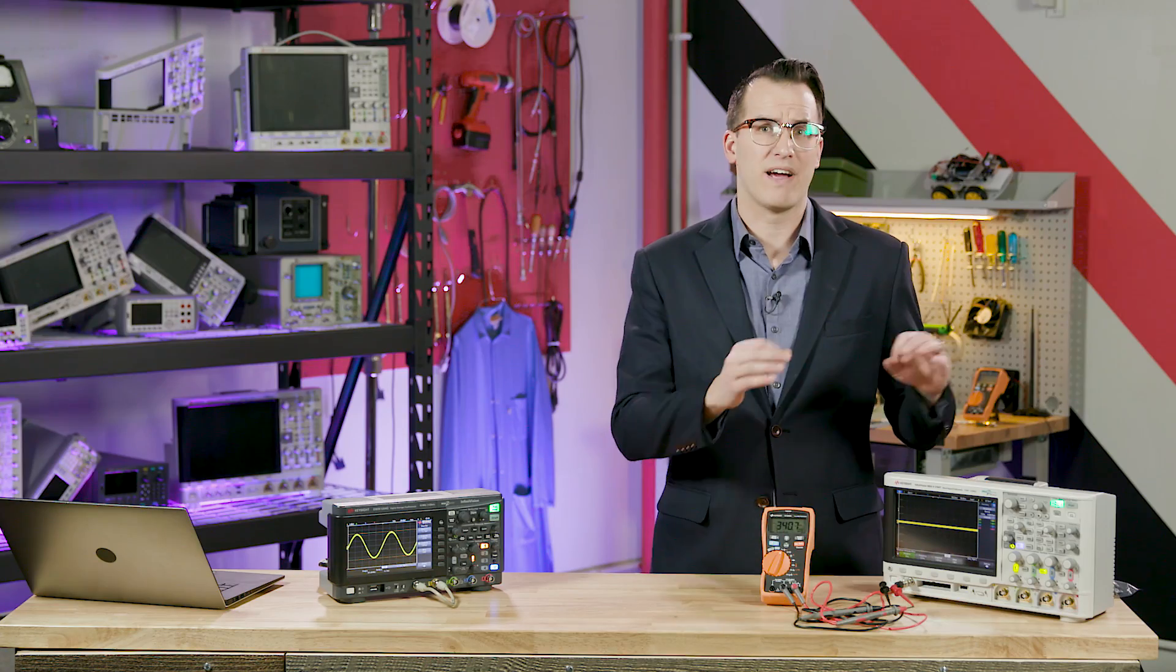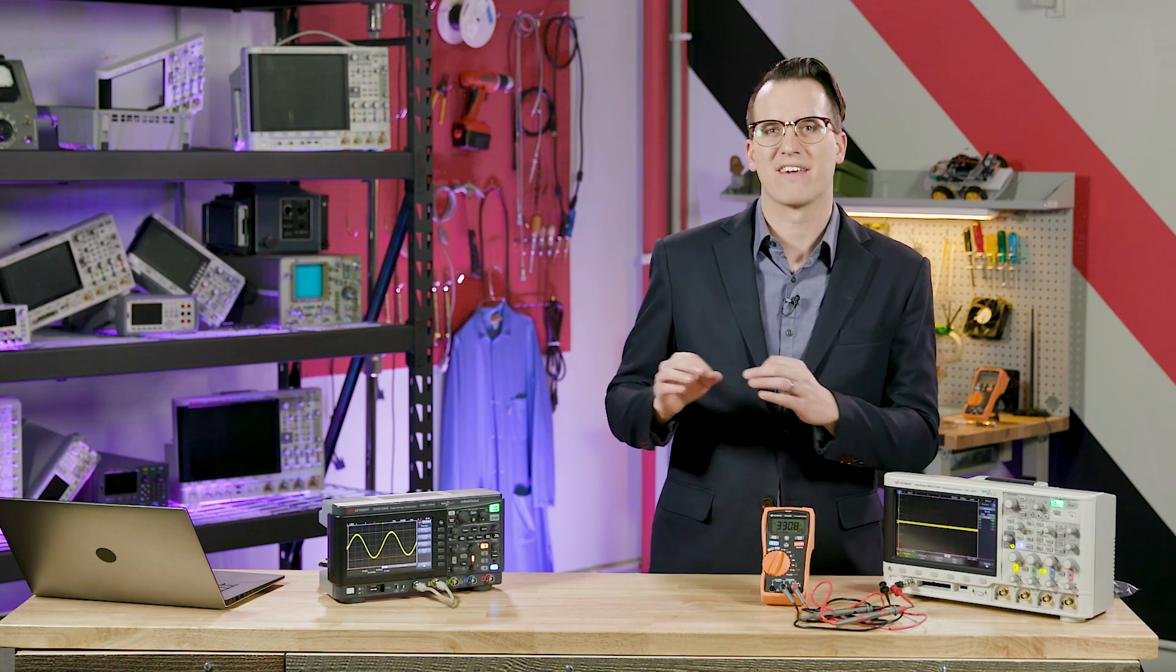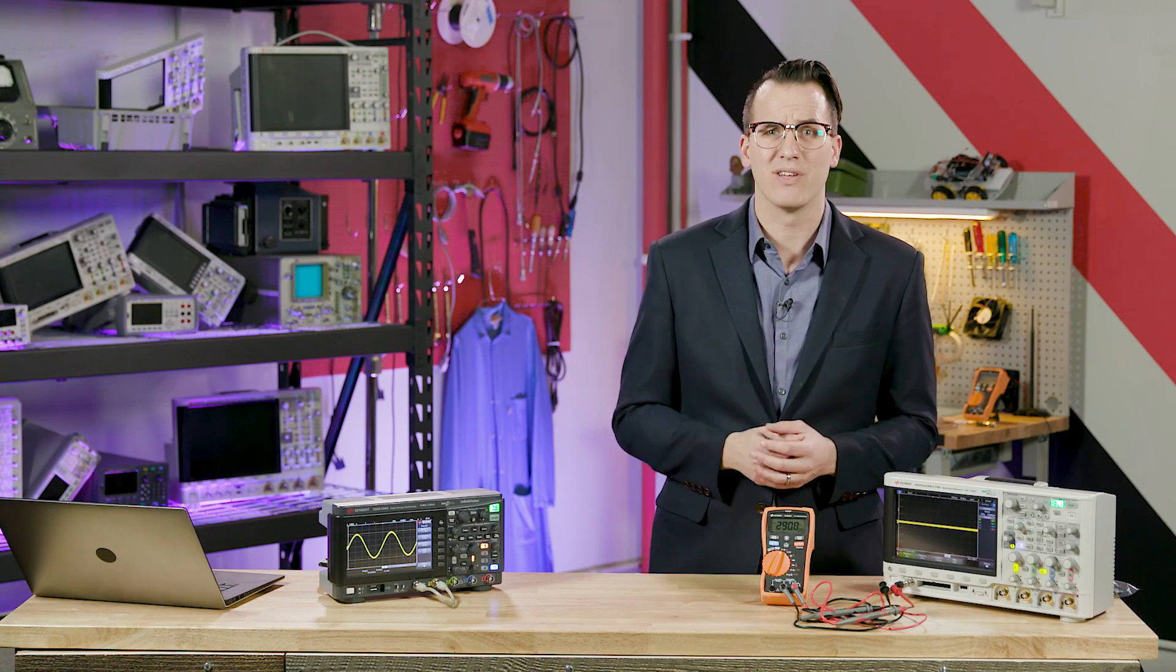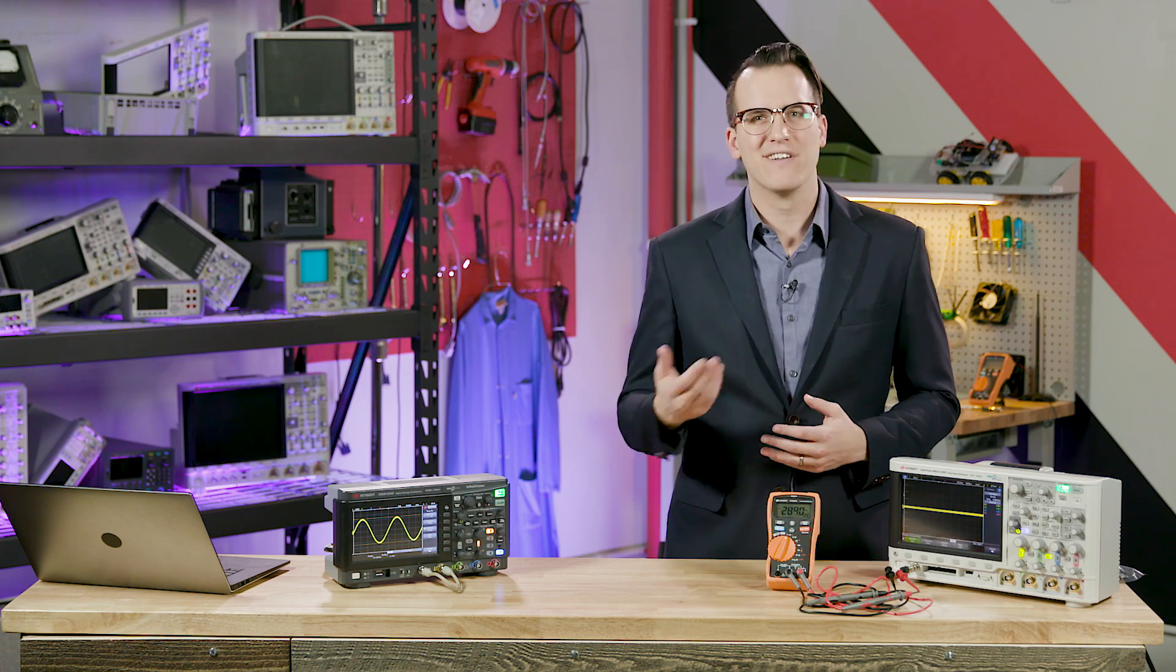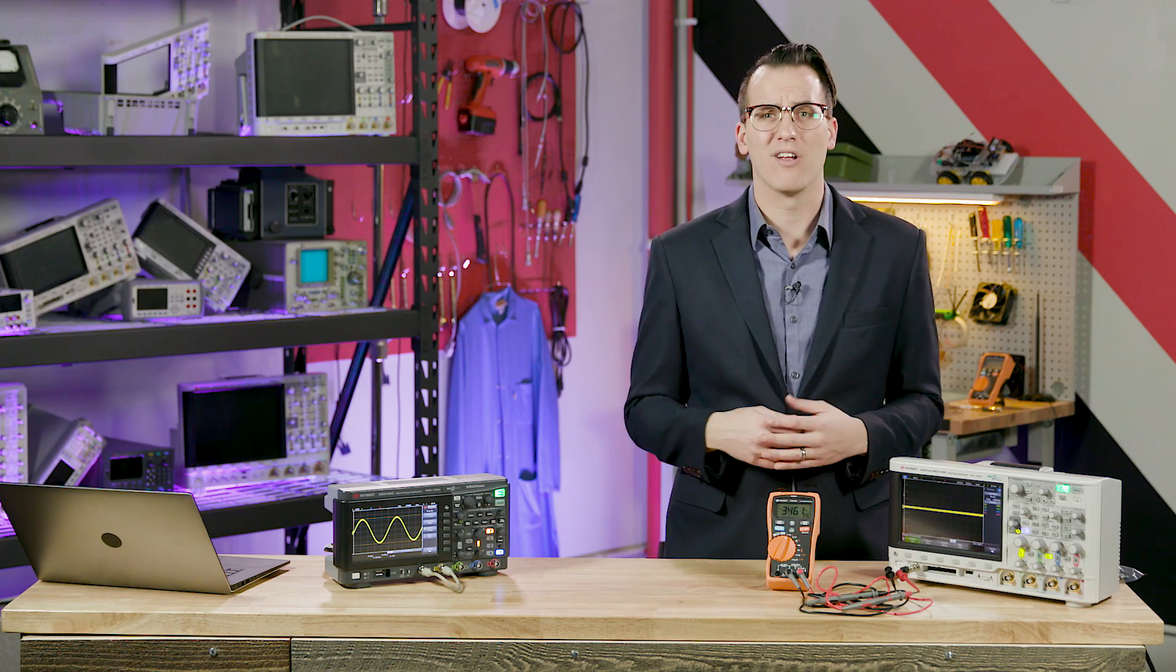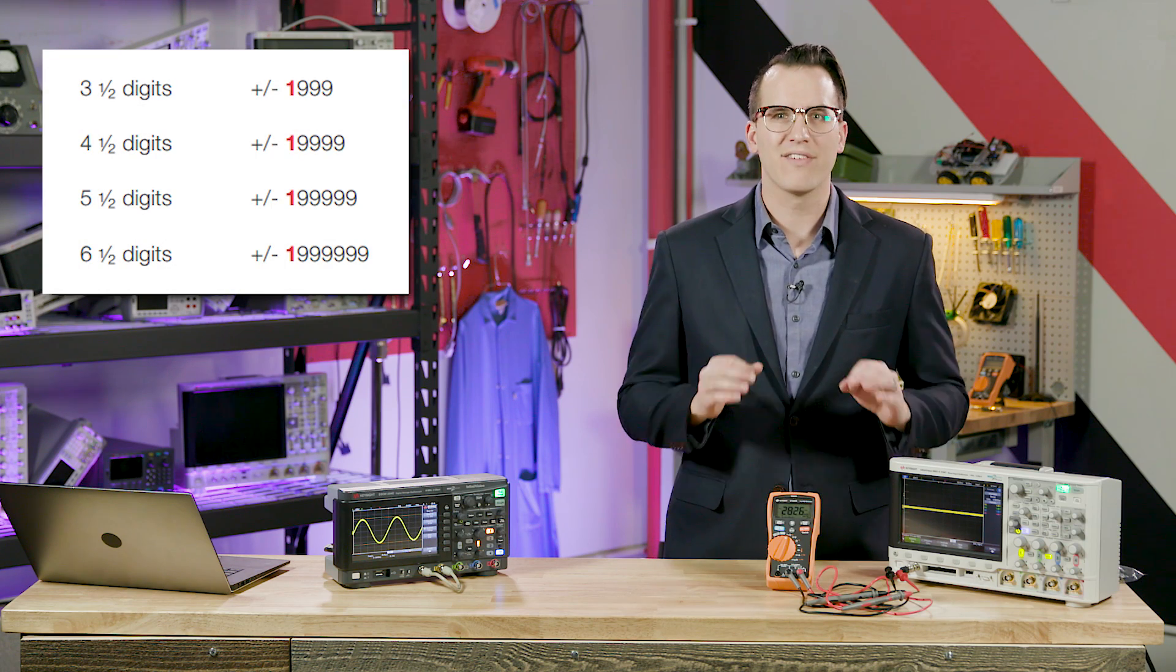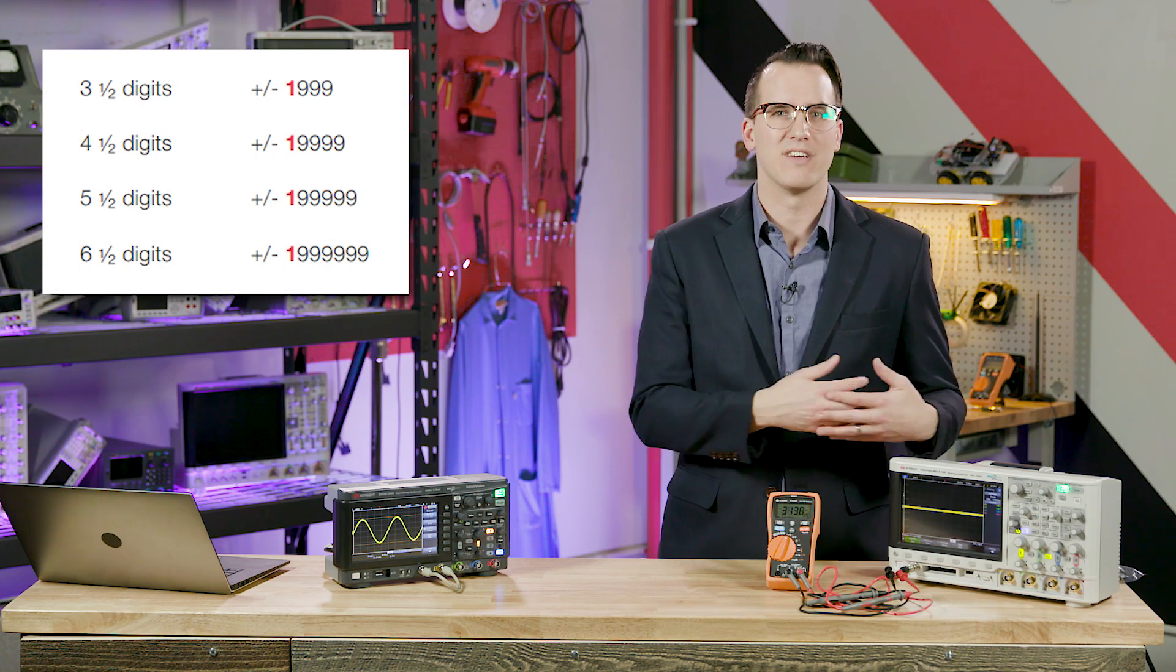Sometimes, though, instead of it being specified as digits, you'll see it specified as counts. So why would you use one or the other, and how do you convert between the two? Well, they both spec the resolution of a DMM, and the difference is really just verbiage, but it can be very confusing. The confusion often lies in the fact that, and this is really important, not all digits on a DMM go from 0 to 9. Often, the leading digit can't go any higher than 1, and sometimes it can go no higher than 3 or 5, and this is due to the internal architecture of a DMM.